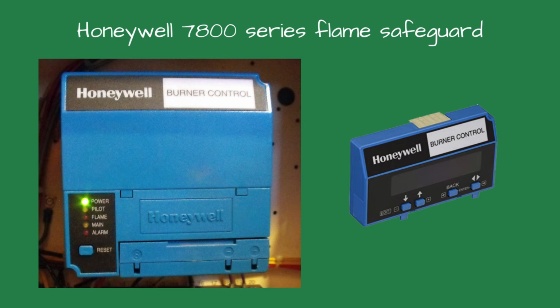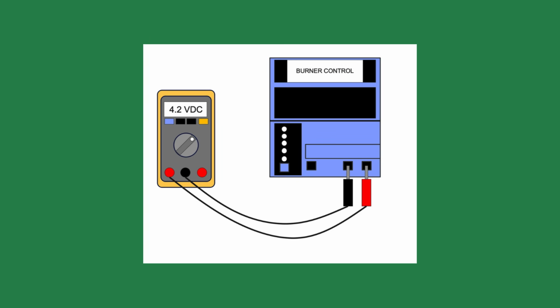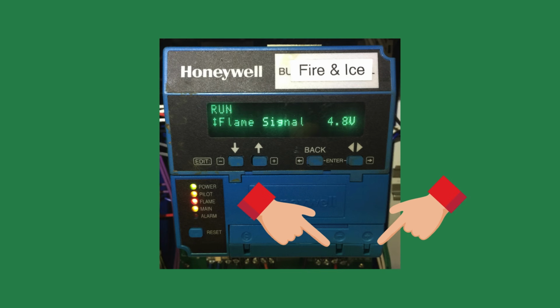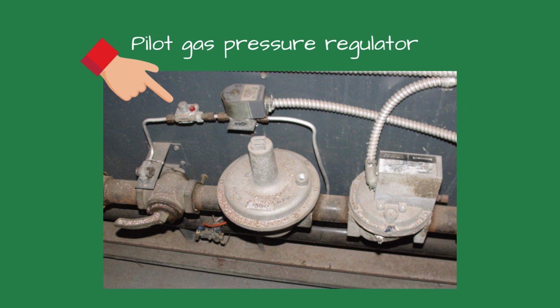Monitor the flame signal. Use your multimeter to measure the flame rectification current. For Honeywell 7800 series, you can connect meter leads to the flame signal test jacks. Observe the signal during the pilot trial. Ideal is 2 to 5 volts DC. The minimum is 1.5 volts DC. If you see a wavering signal, try adjusting the gas pressure open or closed on the pilot regulator.